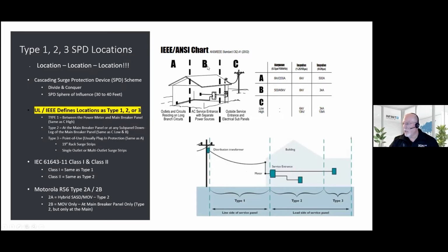Type 2, or the B location, is the main breaker panel or any sub panel down leg of the main. That's Type 2. So most surge arrestors are Type 2. If it is Type 1 rated, by default it's also Type 2 because it's just beefier. So if it can handle Type 1, it can easily handle Type 2. Type 3 is point of use. So that could be a 19-inch rack where the radios are, or network servers, or it could be the operator's console where they throw a power strip under their desk and plug in their monitors and computers and things like that. So anything you plug in is Type 3 or point of use.